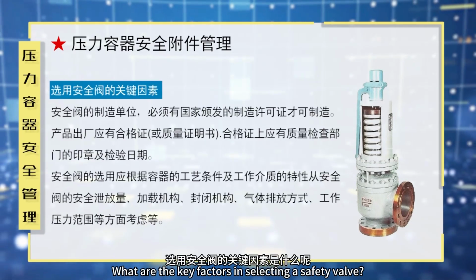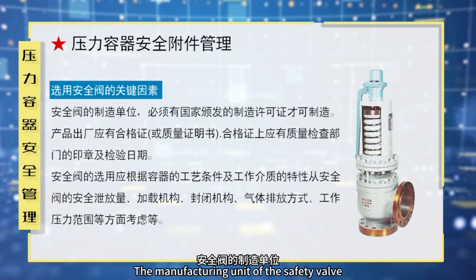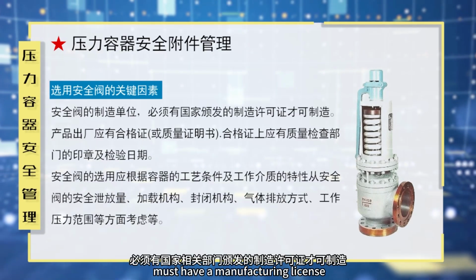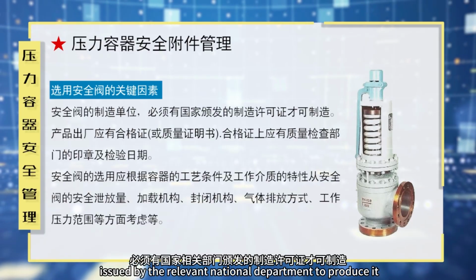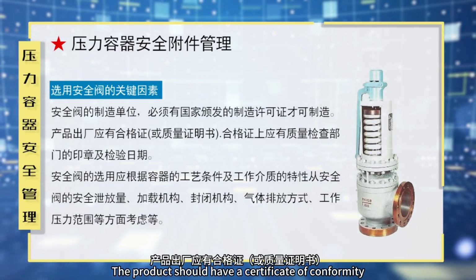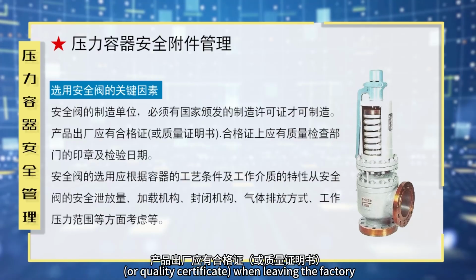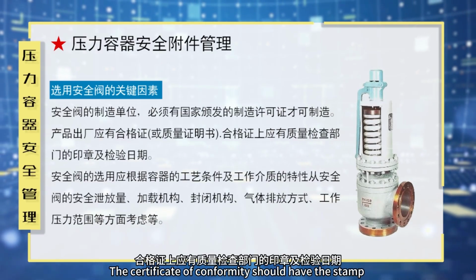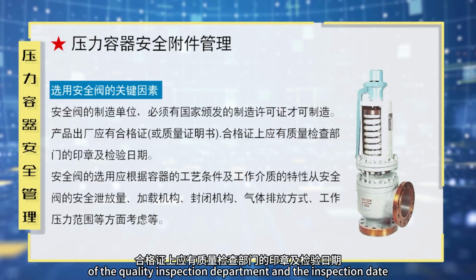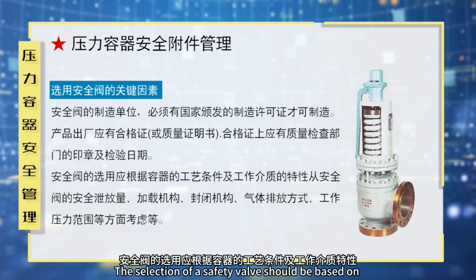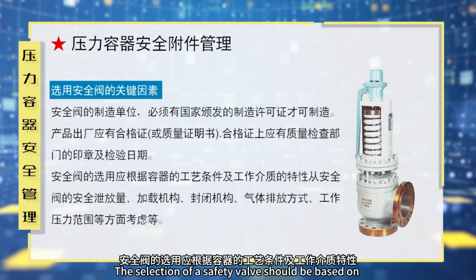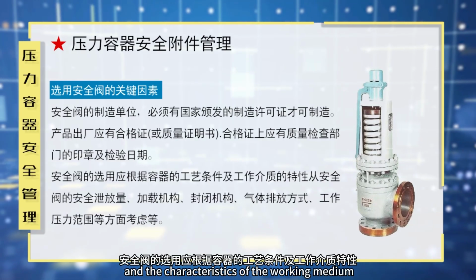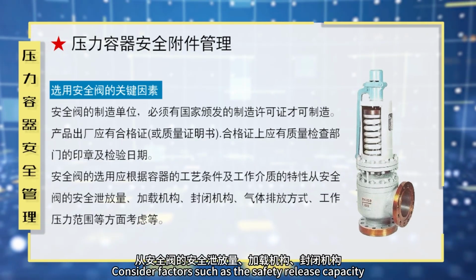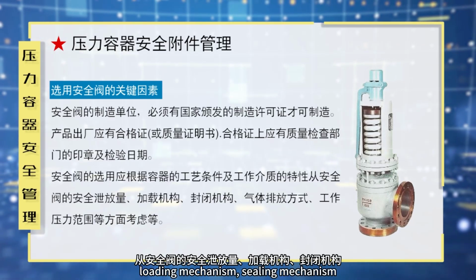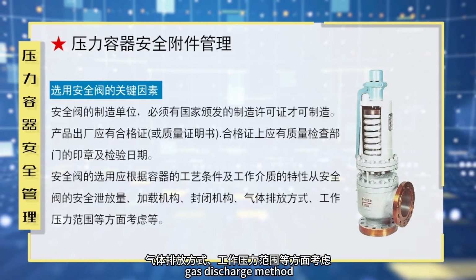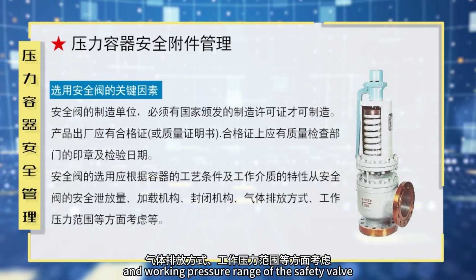What are the key factors in selecting a safety valve? The manufacturing unit of the safety valve must have a manufacturing license issued by the relevant national department to produce it. The product should have a certificate of conformity or quality certificate when leaving the factory. The certificate of conformity should have the stamp of the quality inspection department and the inspection date. The selection of a safety valve should be based on the process conditions of the vessel and the characteristics of the working medium. Consider factors such as the safety release capacity, loading mechanism, sealing mechanism, gas discharge method, and working pressure range of the safety valve.